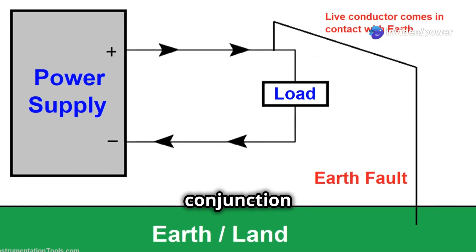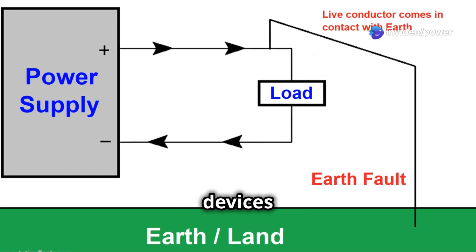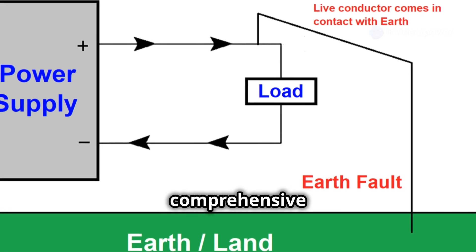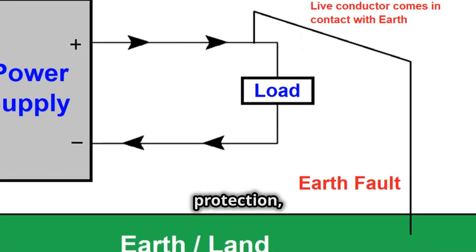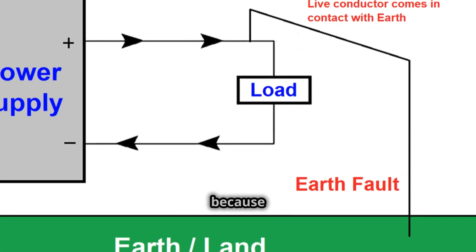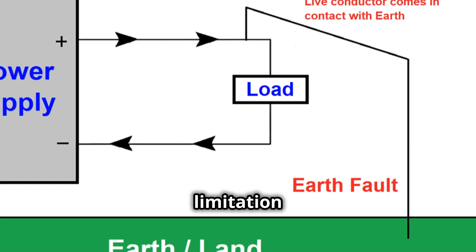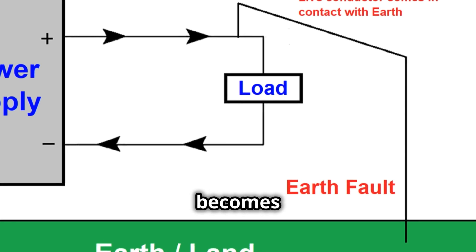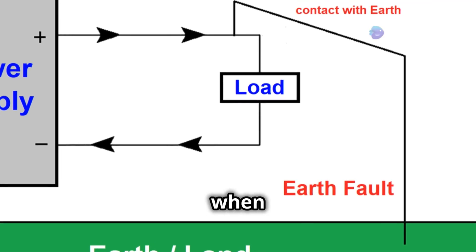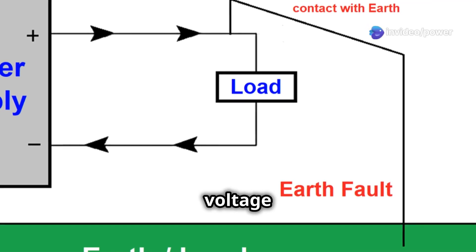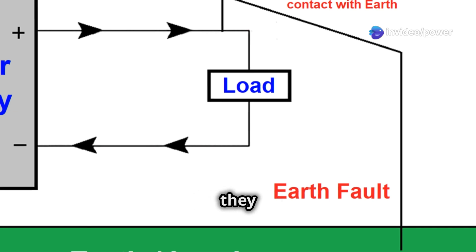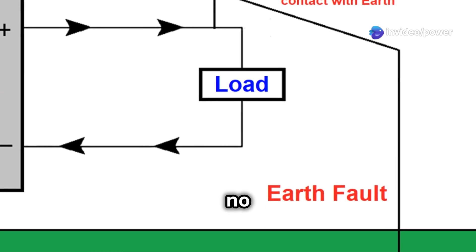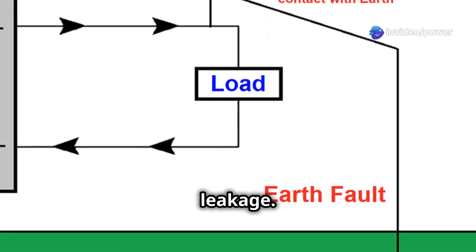However, it's important to remember that RCCBs don't provide protection against overload or short circuits. They're often used in conjunction with other devices like MCBs or fuses for comprehensive electrical protection. It's also worth noting the limitation of ELCBs: they rely on detecting voltage on the earth wire, meaning they won't detect a fault if there is no earth connection.